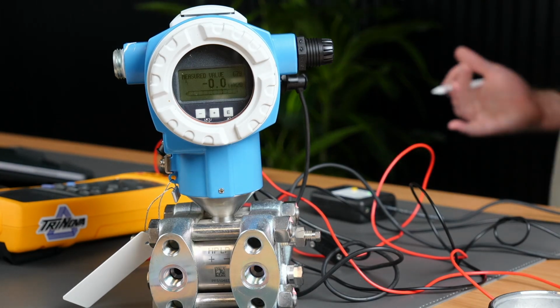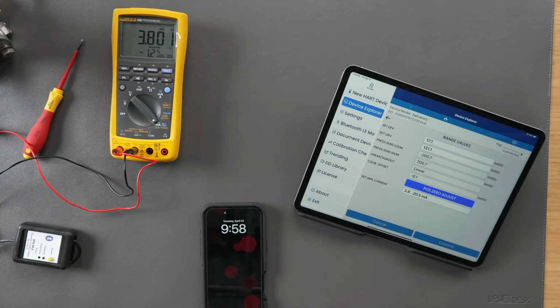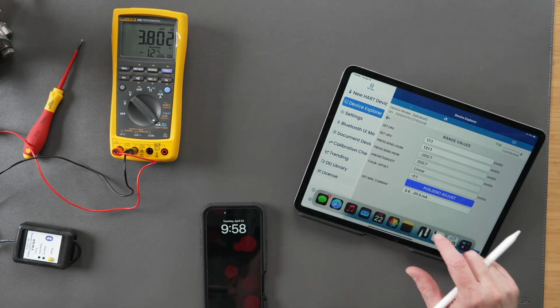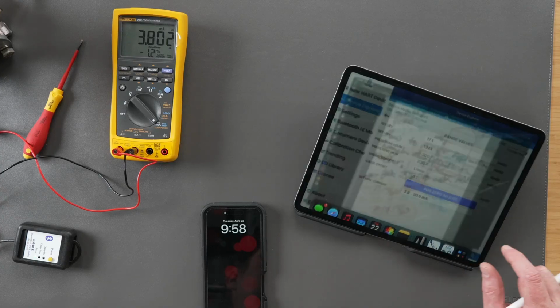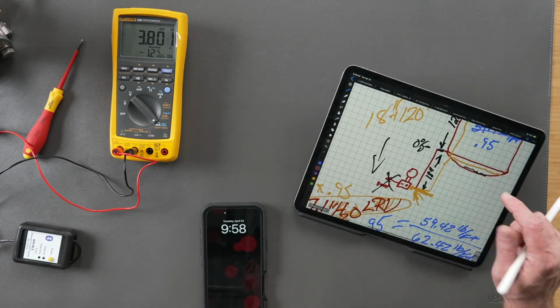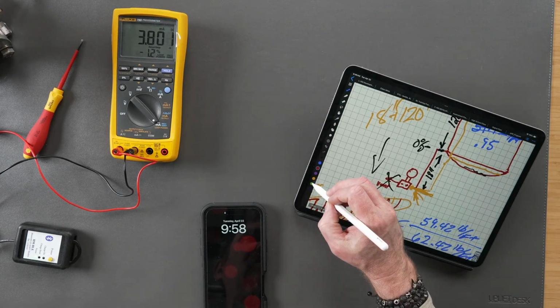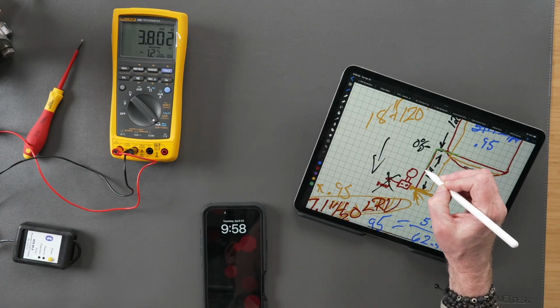Now why would that be? It's because when we were looking at this configuration, we told it that it would always have this pressure right here. But right now, sitting on the bench, it doesn't have that pressure. It doesn't have that elevated zero, okay? So it should be in a fault. It should be in a warning that says, hey, I don't feel my LRV value.